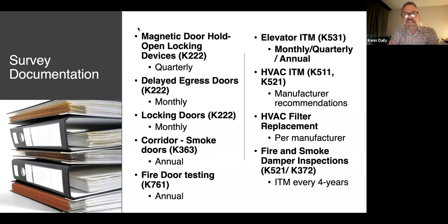Let's see. The next thing, of course, for egress doors is magnetic hold open devices. Again, many places the surveyor will have you pull the fire alarm during survey. What they're looking for is to make sure your magnetic hold open device is released during that fire alarm initiation. And then the biggest citation lately has been where the magnetic hold open devices do release the door, but the door does not actually latch into the frame. So you quarterly check during a fire drill, you would check to make sure all your doors that are being held open by magnetic hold open devices are closing and latching into the frame.